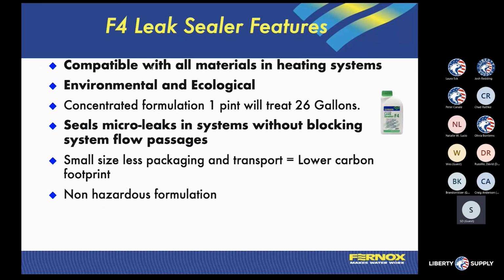We do make a leak sealer. This works on all materials, whether it's PEX, galvanized, copper, stainless, brass, all of the different types of systems. It's the same formulation from concentrate. We're going to use 26 gallons of system fluid for every one bottle of leak sealer. You can combine leak sealer with other products, so if you put F1 in there and you also have a leak, you can also add RF4 into that system to seal up the leak.